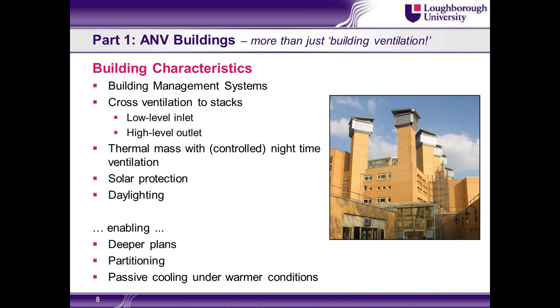Okay, so a little bit more about ANV buildings. The way I describe this is, an ANV building is more than just building ventilation. It's more than just ventilating your bedroom, if you like. ANV buildings have a building management system. They'll often have cross ventilation from one side to another, and there may be vertical ventilation stacks on the opposite side of that occupied space. So there'll be low-level inlets and high-level outlets to give us that buoyancy driving pressure.